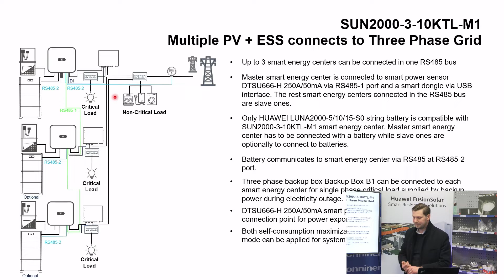The communication with the backup box isn't Modbus RTU like the other devices—it's just a simple high and low level signal. When AC is present, the backup box outputs a high voltage level. When it disappears, it drops to zero, triggering the switch, and we're disconnected from the grid. The inverter then works as a backup in off-grid mode.